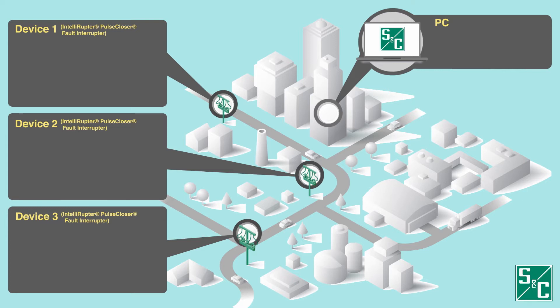We will be using a system consisting of three IntelliRupter Pulse Closer Fault Interrupters and a PC for remote connections as an example. We'll demonstrate use of the cellular network as a primary network for IntelliRupter Pulse Closer Fault Interrupter monitoring and control, and also show use of the cellular network in conjunction with a private field area network constructed using Speednet radios. We'll configure the gateway to operate in the VPN network interface mode using OpenVPN.